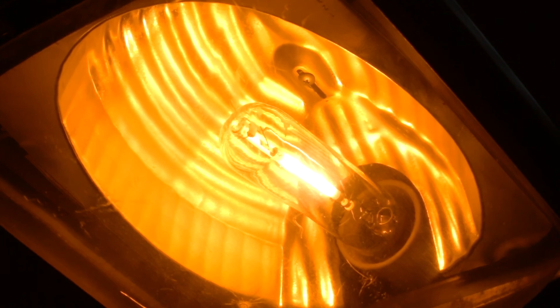170 watts now. Total system power from the ballast and the lamp itself. It's pretty much full power. We've got a power factor of 90.